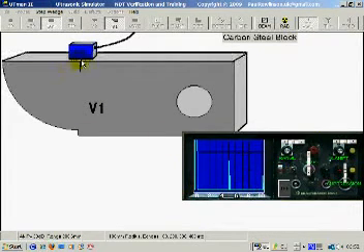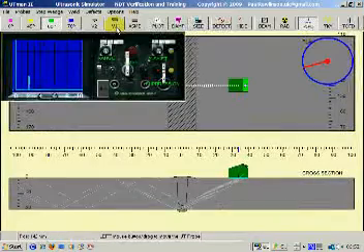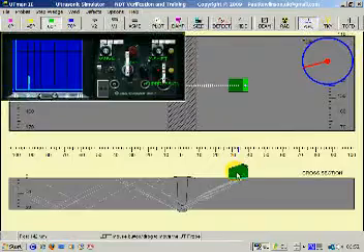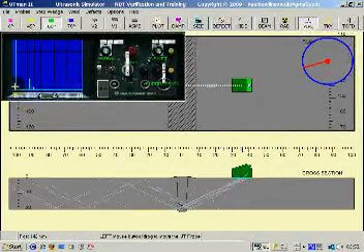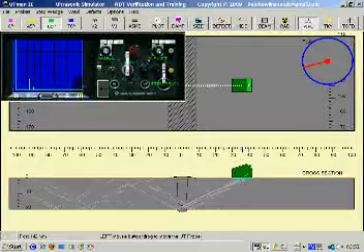So we have an echo of 100 millimeter radius here, and the second echo represents therefore total range of 200 millimeters from left to right. Increase the amplitude. Re-click the V1 button on the top to exit the calibration mode. We now have a screen reading of 0 to 200.